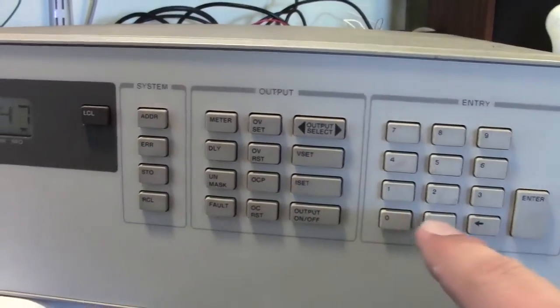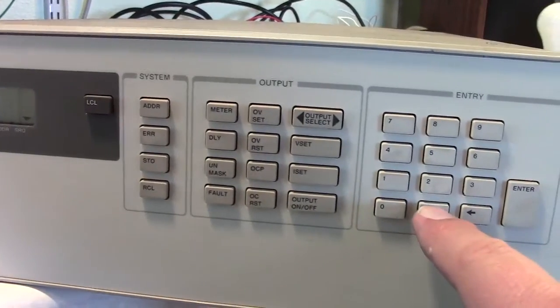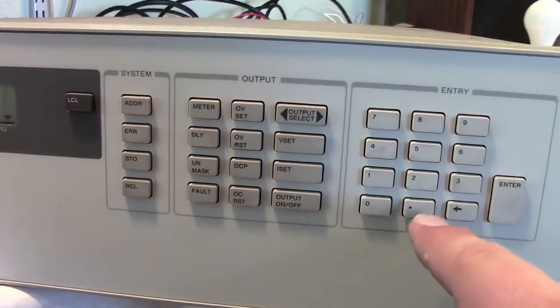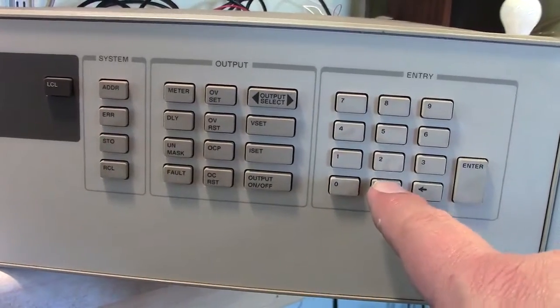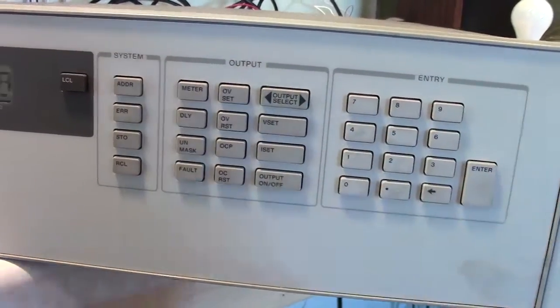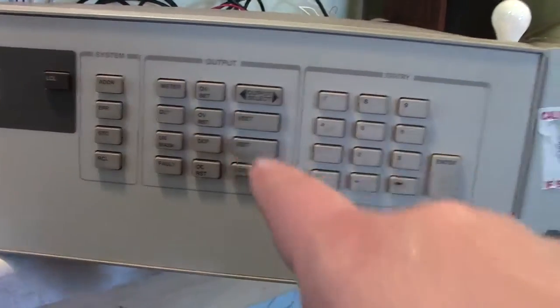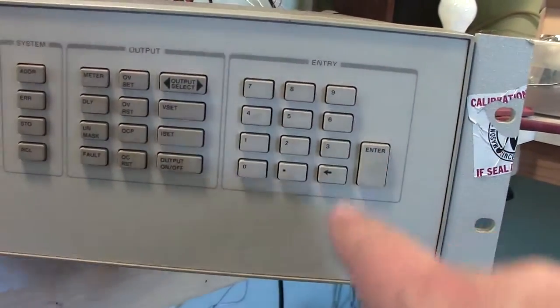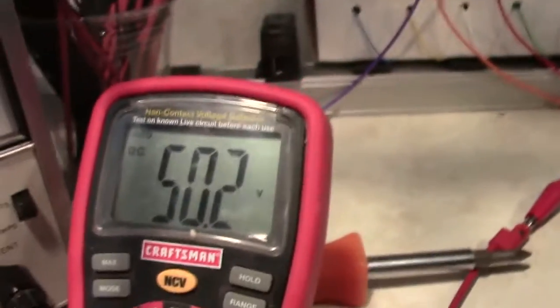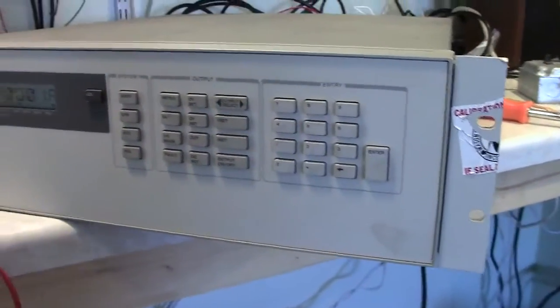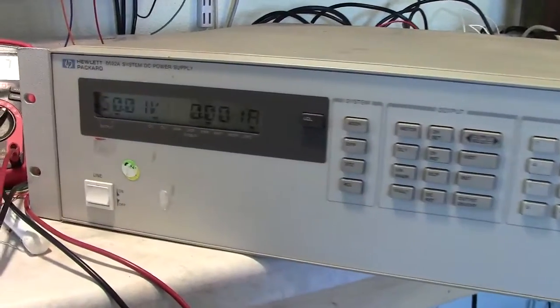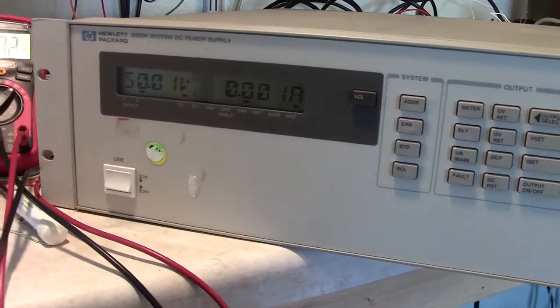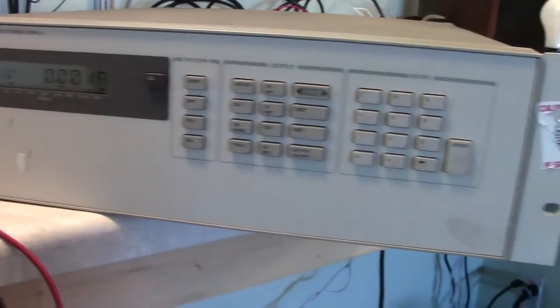Let's kick it up to 50 volts here. V set at 50.75. No, didn't like that. V set 50 volts. Oh, we're at 50 volts here, and this one is reading 50 volts out. Okay, well, output number 2 is working. This is yet another piece of test equipment I'm going to use for the SolOhm multimeter calibration.